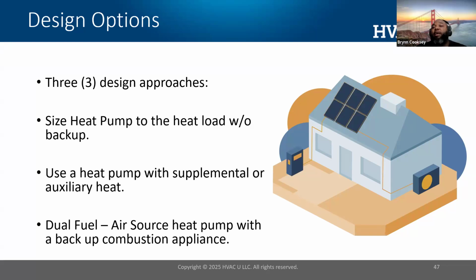And then third, I have a backup source called dual fuel. Dual fuel is using a heat pump as your primary source and then using the opposite source, such as a backup gas furnace, to stand in when the heat pump is either tapped out as far as capacity or is too costly to run due to rates. So these are three design approaches that you can use.